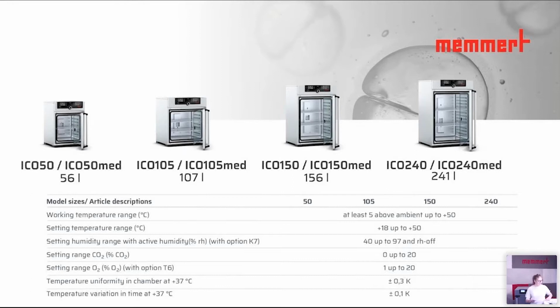All right, moving on to our ICO line. We are very proud to offer our ICOs in 4 different sizes, starting with the smallest size, the ICO 50, going over the ICO 105, continuing with the ICO 150, and ending in the biggest size, our ICO 240. The model names are all associated with the interior volume, as seen down below. Our working temperature range starts at least 5 degrees Celsius above ambient and goes up to plus 50 degrees Celsius. Our humidity setting range with active humidity is between 40 to 97%, plus an additional humidity off feature. Our CO2 setting range is between 0 to 20%, and in case you also want to control O2, you have that option by adding option T6, and you will be provided with an O2 setting range of 1 to 20%.